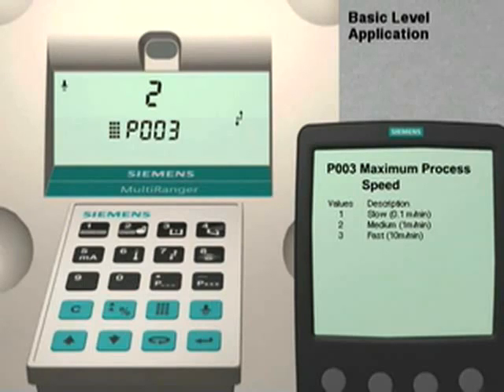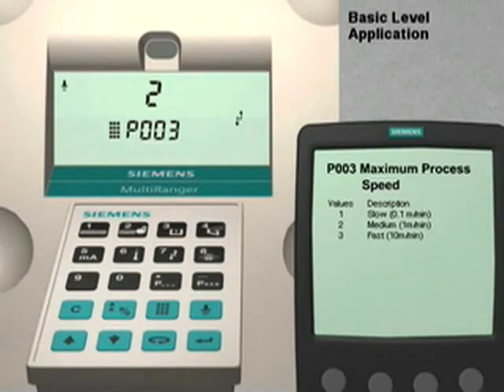Parameter number 3 is used to match the response time of the multi-ranger to the rate of level change within the vessel. The factory default is 2 for a medium rate of change. We will leave this parameter set to the factory default.